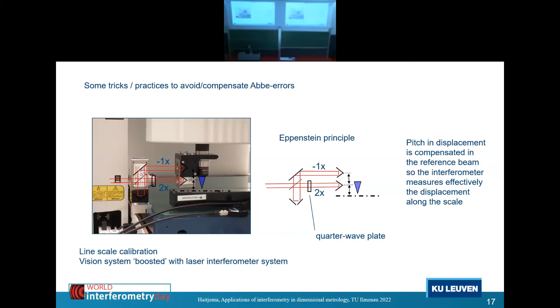It is very simple. And also here, a vision system, it's a commercially available vision system. It is this time also boosted by a laser interferometer. And altogether, with the vision system, you can measure the edges, and with the laser, you can measure the distances. Then another example is the calibration of step gauges. Step gauges are also used in calibrating CMMs or other distance measuring instruments. Even calipers you can calibrate using a step gauge.